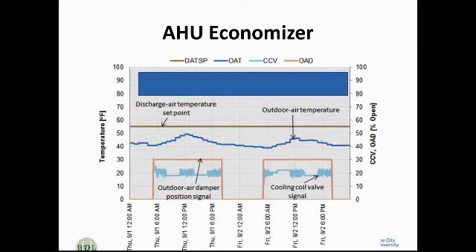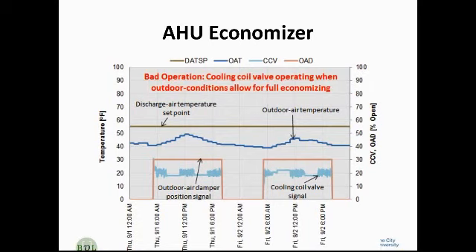Now here's another economizer example where once again I've got a 2-day period, and you can see that the discharge air temperature set point, that's the air coming out of my air handler, is set for a constant 55 all day and all night. The outdoor air temperature varies from 40 to 50 degrees Fahrenheit, depending on the time of day. And you can see that the outdoor air damper position signal is open during occupied hours. Well, it's good that the outdoor air damper is open during occupied hours.